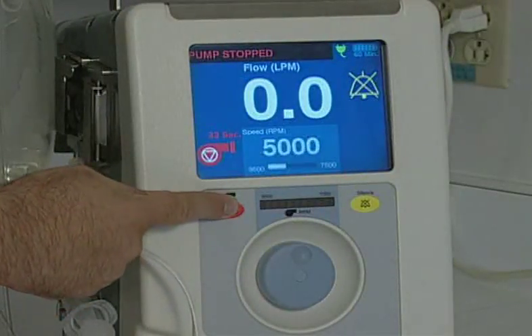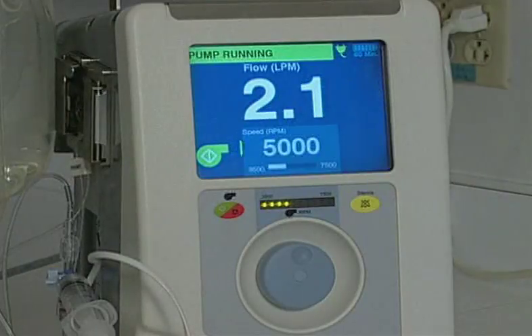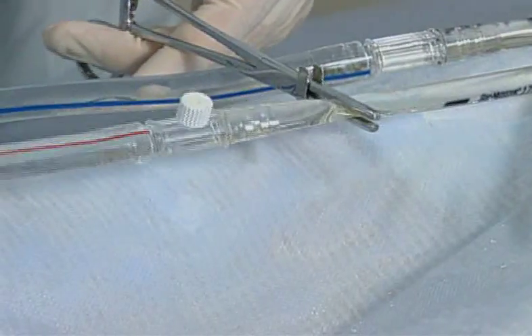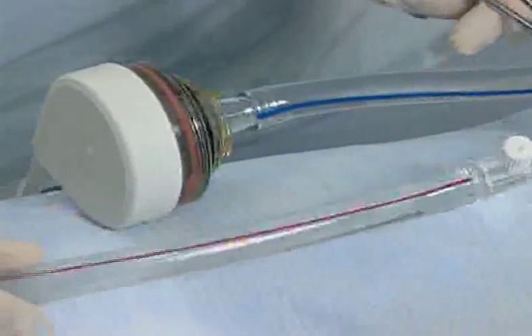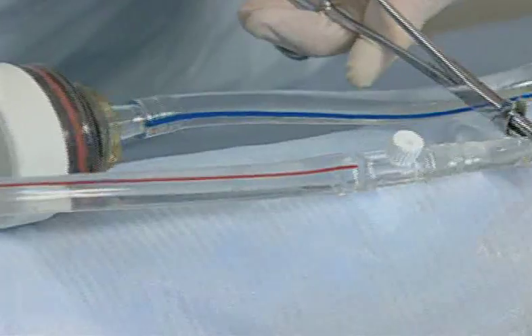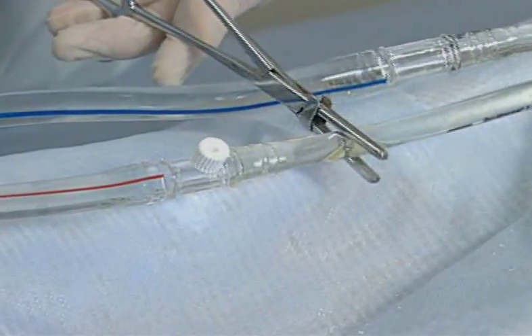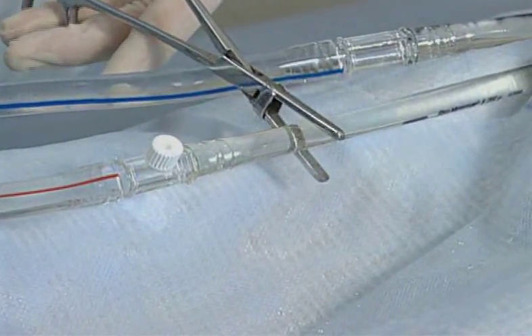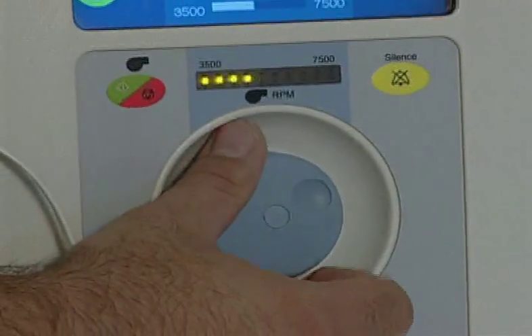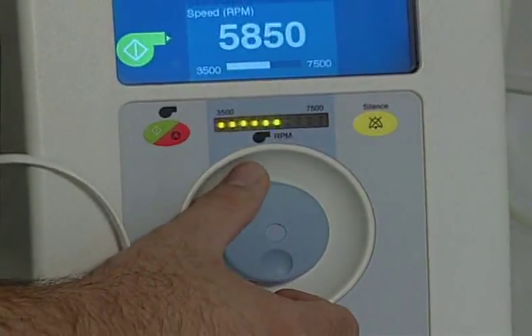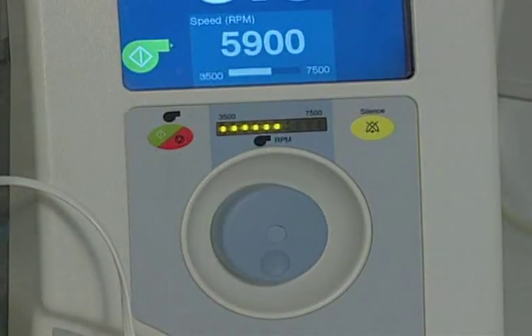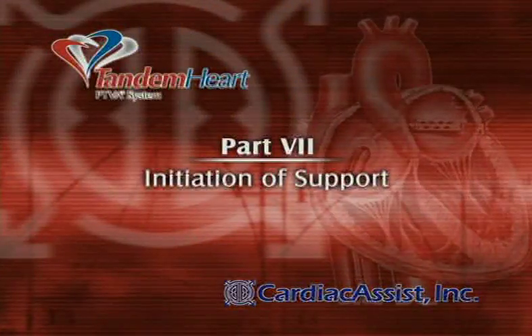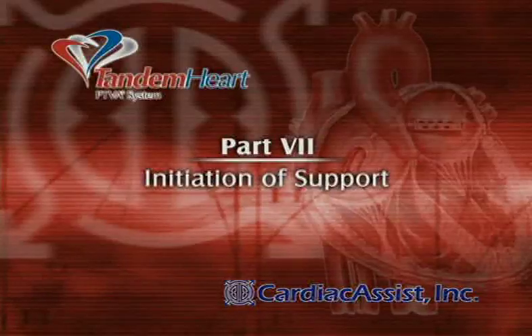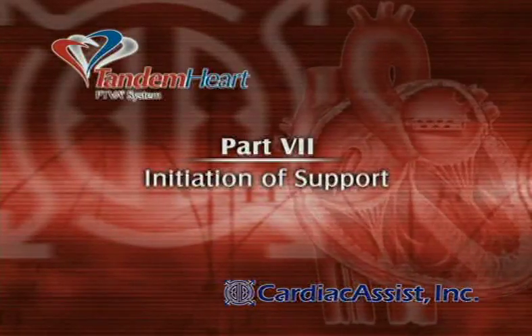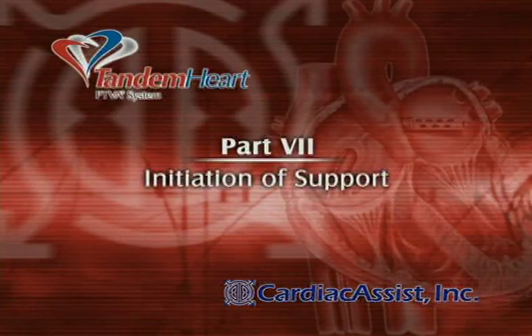Start the pump, which will start at 5,000 RPMs. Check for air bubbles. If tubing and pump are air-free, slowly release the clamp on the arterial cannula. Increase the pump speed until the desired level of support is achieved. Initiation of support. Now that the system is in operation, the pump should be secured to the patient's thigh.